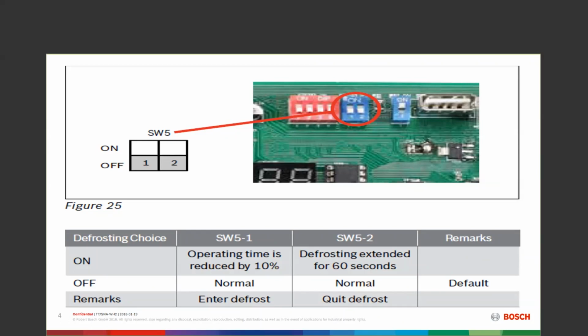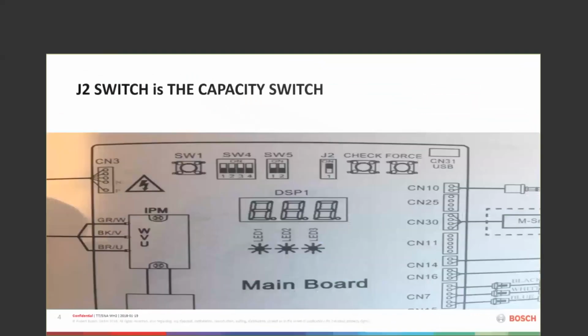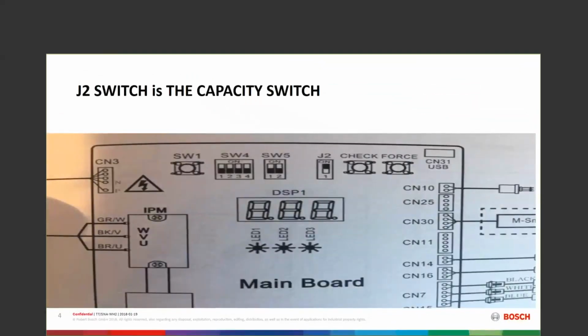To me, it's a very neat situation, neat logic behind the defrost. The J2 switch is nothing more than a capacity switch. It is a switch that allows me to deregulate my 3-ton to a 2-ton, allows me to deregulate my 5-ton to a 4-ton, what we would call just taking the top end off of this system and that kind of thing. For 3.5 years, we've told people to leave this switch alone, allow this machine to deregulate itself.